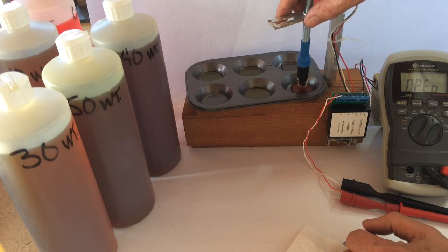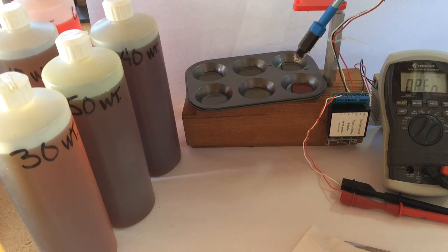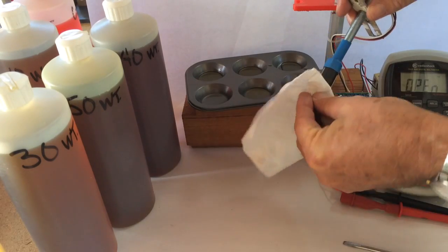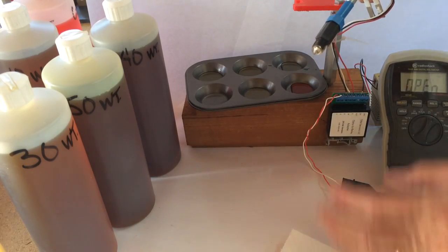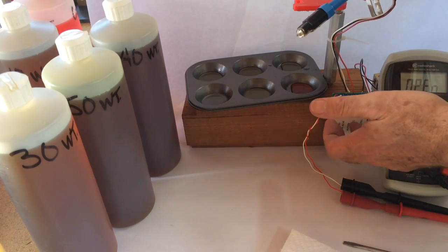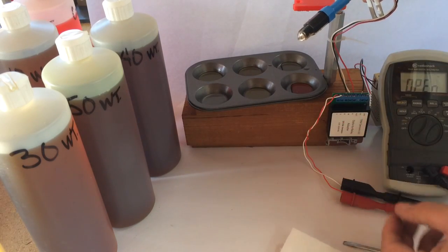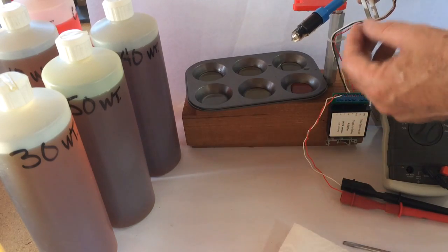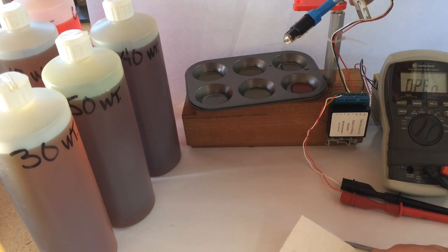it resets. So I would say it's a pretty good demonstration. Test results are very favorable. It tells me that the combination of this probe with this adapter will generate a dry relay contact that switches on when in contact with the oil and switches off as soon as the oil is removed from the probe.